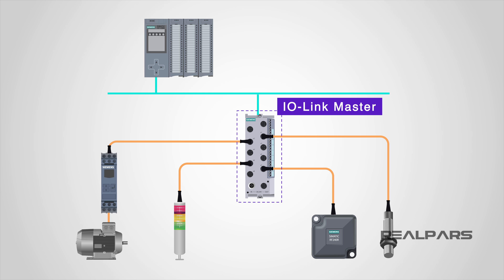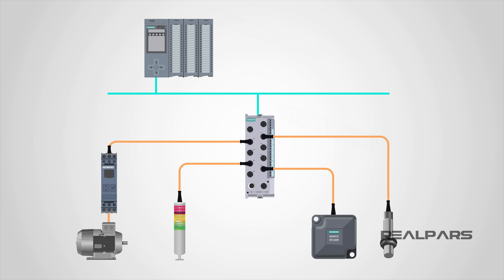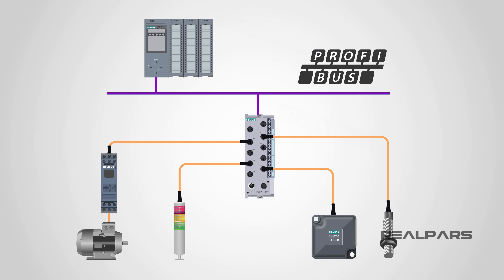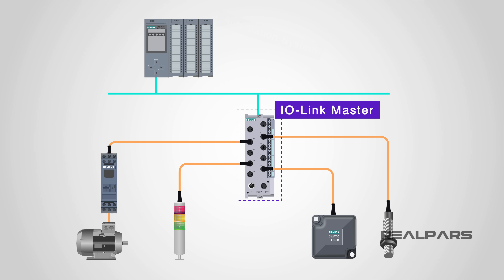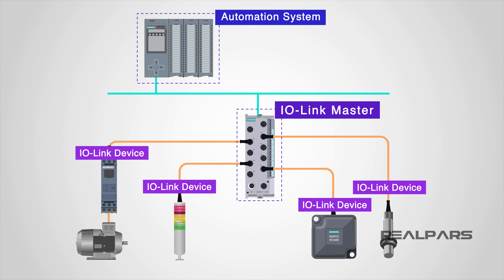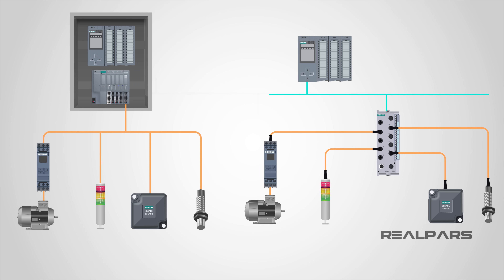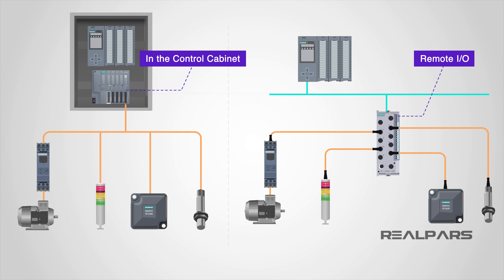The IO-Link master is capable of processing digital signals and analog values. Its versatility means it is capable of integrating into existing systems and can communicate using the industry-recognized PROFINET, PROFIBUS, or MODBUS, to name a few. The IO-Link master establishes the connection between the IO-Link devices and the automation system. As a component of an IO system, the IO-Link master is installed either in the control cabinet or as remote IO, directly in the field.